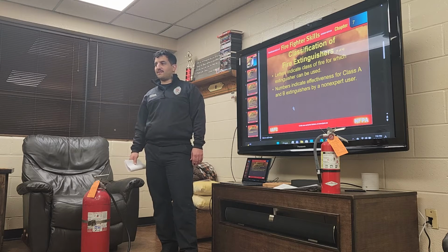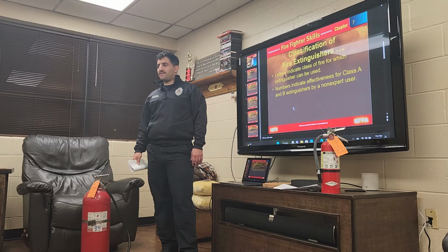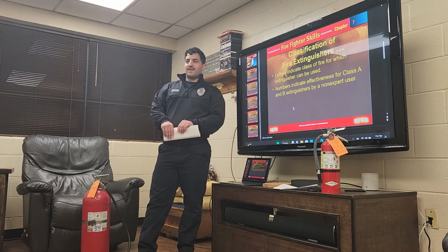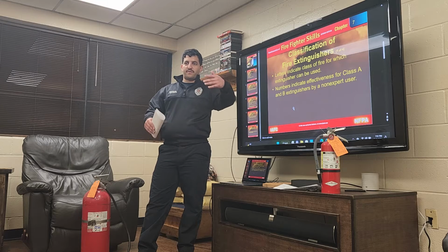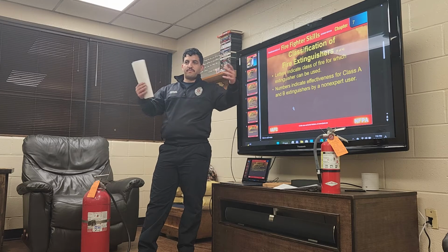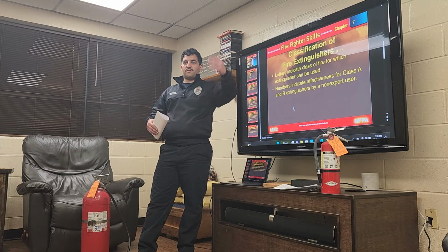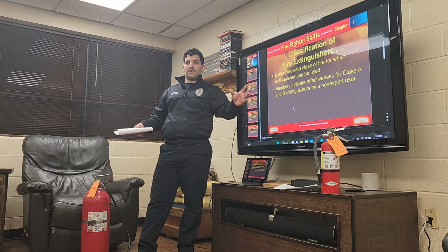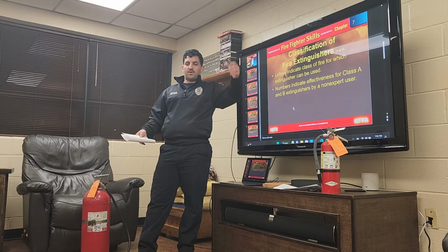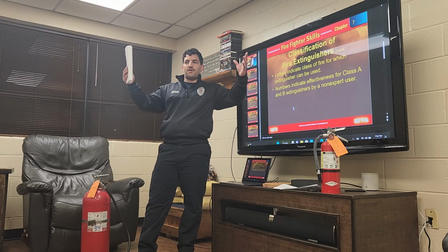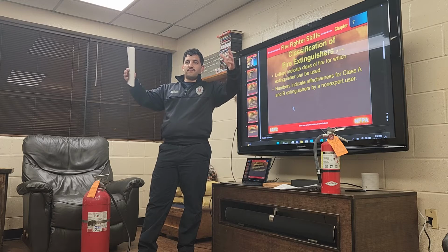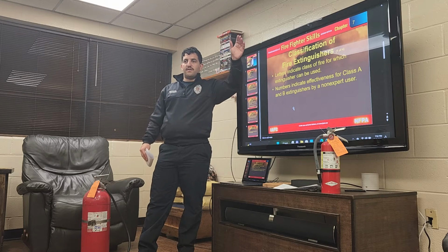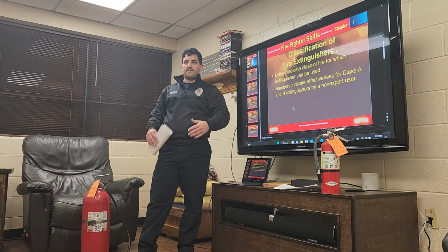Yeah. I used a water extinguisher on a mulch fire at a restaurant. Somebody threw out a cigarette and caught the mulch on fire. Okay. So, go to the grease fire. They say that if it's a grease fire, it's going to catch the cabinets. Sometimes it'll catch the cabinets and other woods on fire right on top, and that wouldn't classify as a Class K because now you've got ordinary combustibles on fire. It may have started with the grease, but it's going to evolve into the wood and everything surrounding that, which is usually ordinary combustibles. So you spray that down, and obviously you don't want to spray water at the grease because that will just have a violent reaction.